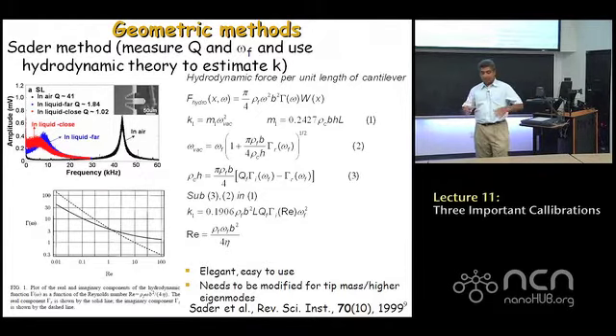This is the key thing. The key thing is, as I said, the one thing we cannot trust from the manufacturer is the thickness, but we can trust the width and length data they provide, right? Because the length and width come from the mask that's used to prepare those cantilevers. The thickness is not decided by the mask dimensions. Thickness is decided by the etching process and the control of the etching process. So Sader's method utilizes basically information about just the length and the width, which you can get from a scanning electron image, or you can take the manufacturer's number and it's within 5% correct.